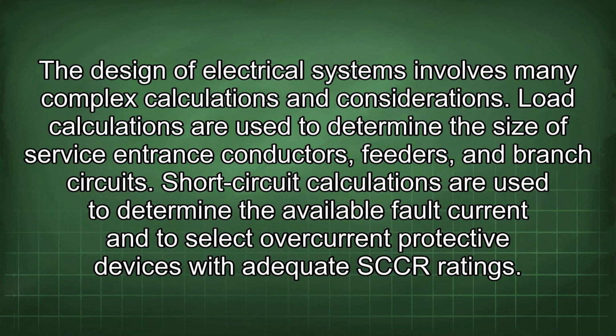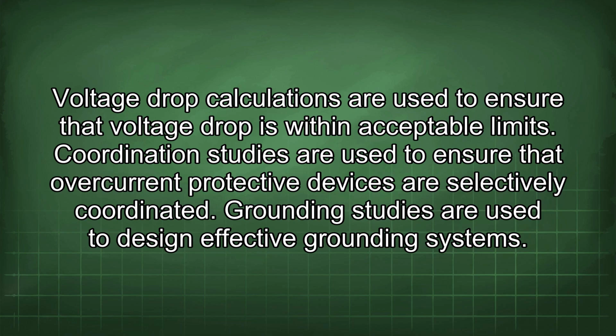The design of electrical systems involves many complex calculations and considerations. Load calculations are used to determine the size of service entrance conductors, feeders, and branch circuits. Short circuit calculations are used to determine the available fault current and to select overcurrent protective devices with adequate SCCR ratings. Voltage drop calculations are used to ensure that voltage drop is within acceptable limits. Coordination studies are used to ensure that overcurrent protective devices are selectively coordinated. Grounding studies are used to design effective grounding systems.